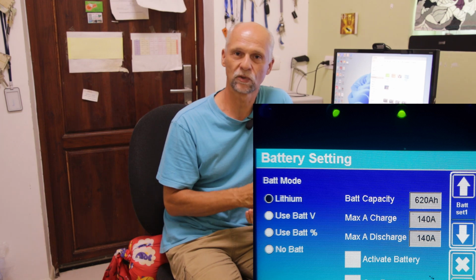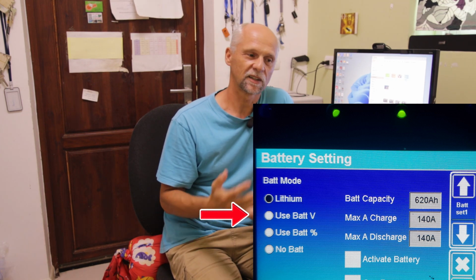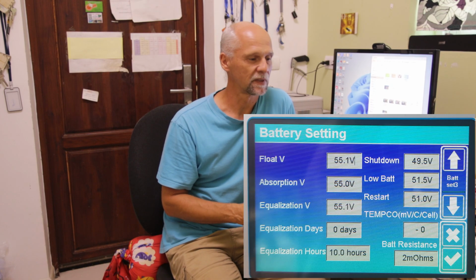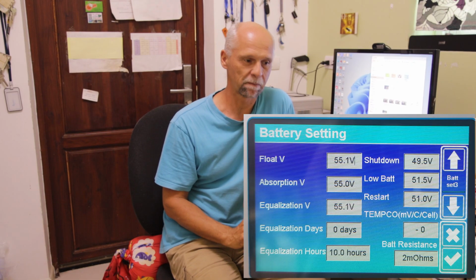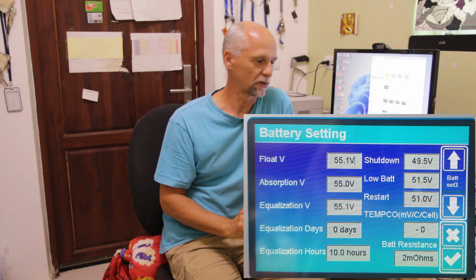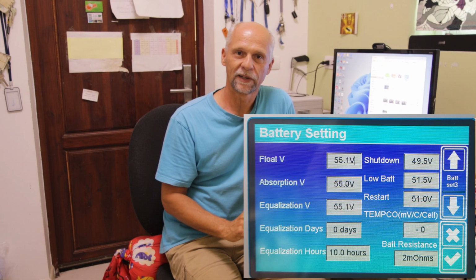So is there a way for us to counteract this situation? And there is. What I had to do is go to the fallback procedure, which is the inverter forcing the battery. This is when you go to the battery settings in the Deye inverter, and instead of using lithium mode, you go to the use voltage mode, right? Because then it is again just a simple charge controller where you can set your absorption voltage and your floating voltage. So when you set your absorption voltage at a value where the batteries will start balancing and then the current is reduced, you can give the balancer precious time to do its job.